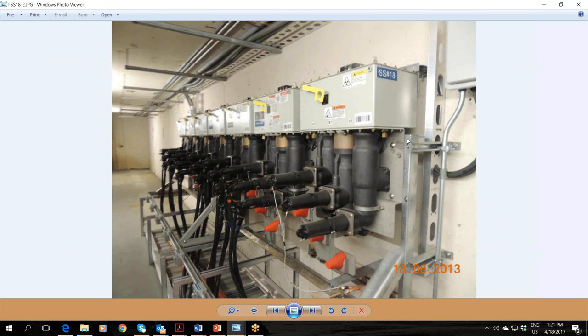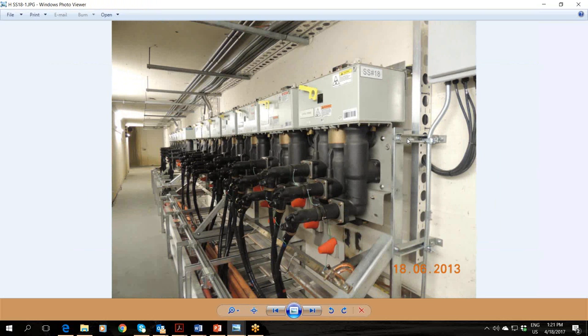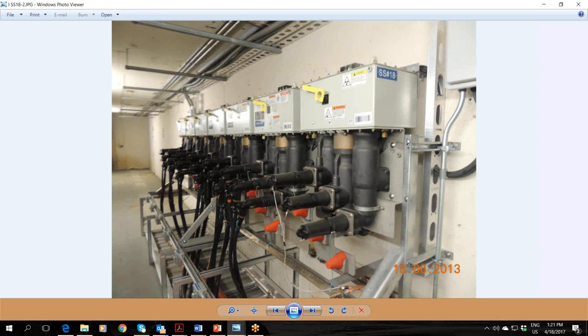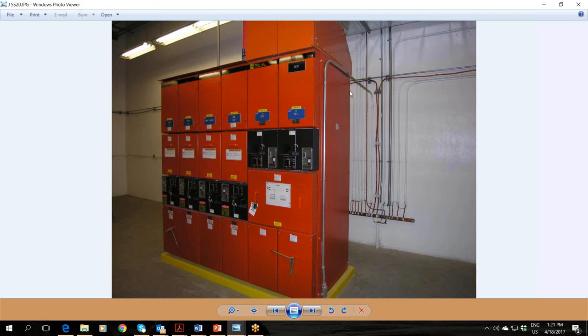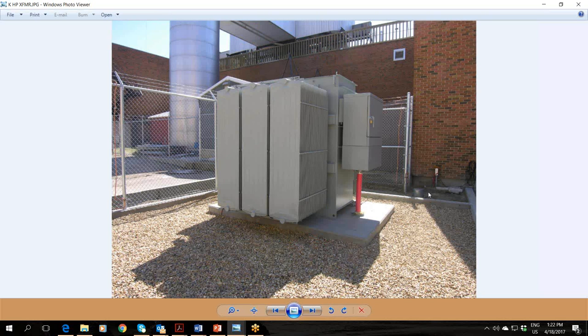There's a picture of the other half of it, so sectionalizer 18, the blue side. And again, you can see that they're two physically different lineups, blue versus white. Again, close proximity, but two different physical lineups. This is a different picture of a different type of sectionalizer. This is again using vacuum switches. This is just the blue side. I don't have a picture of the white side, but you have your main incomer, your main outgoer, and then your feeders out to the different buildings.